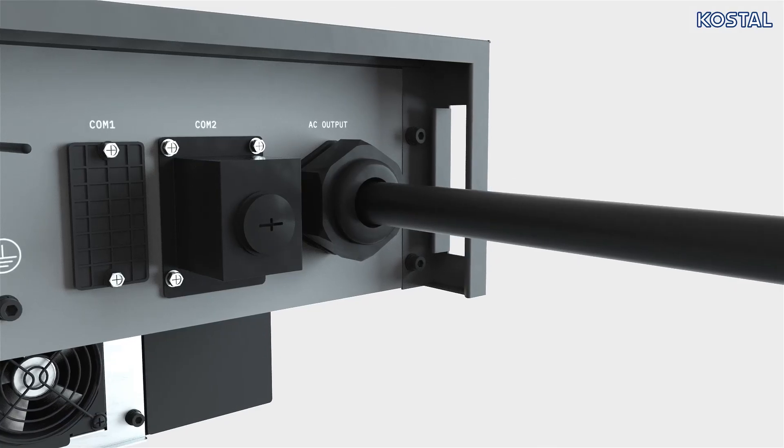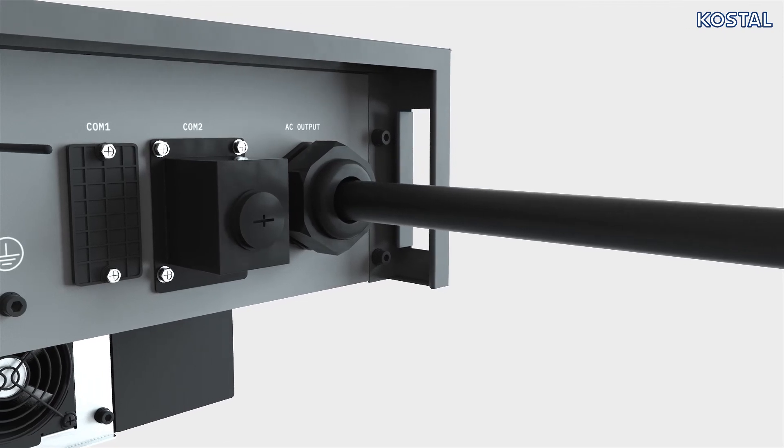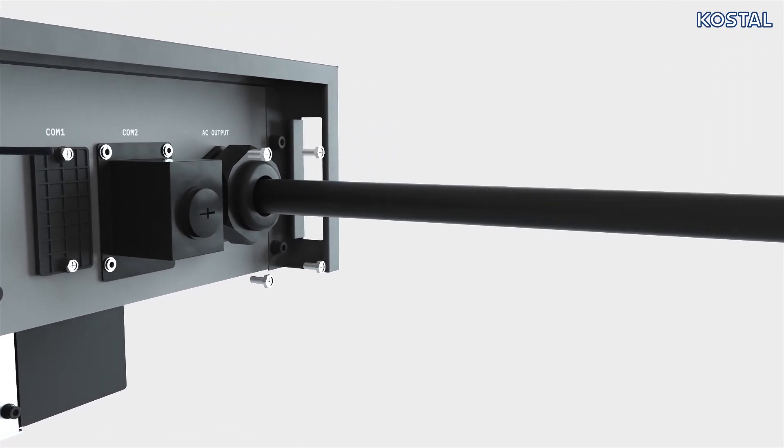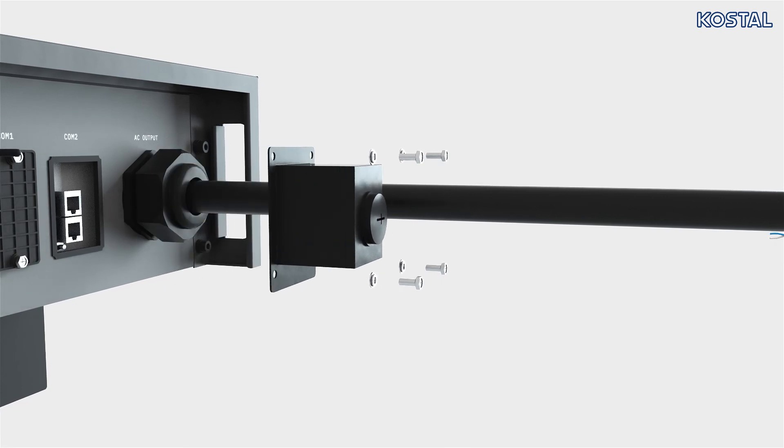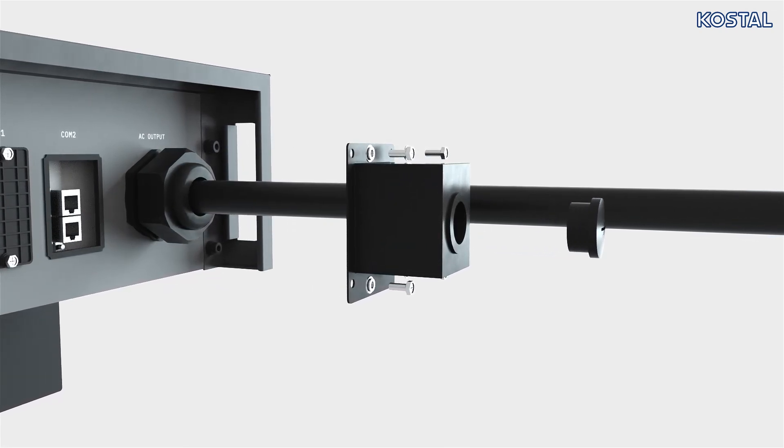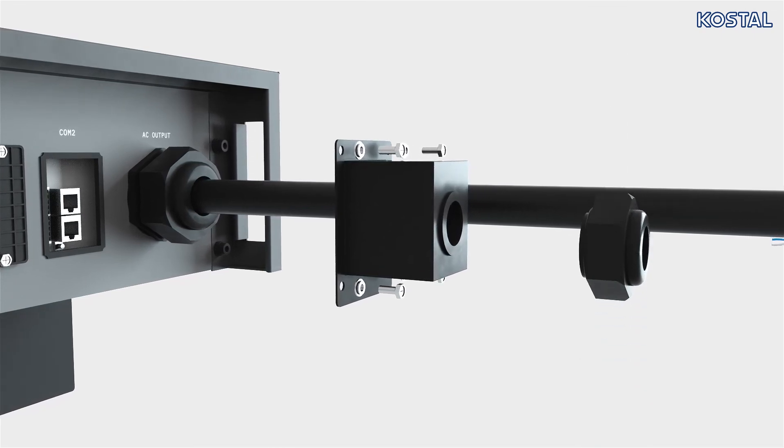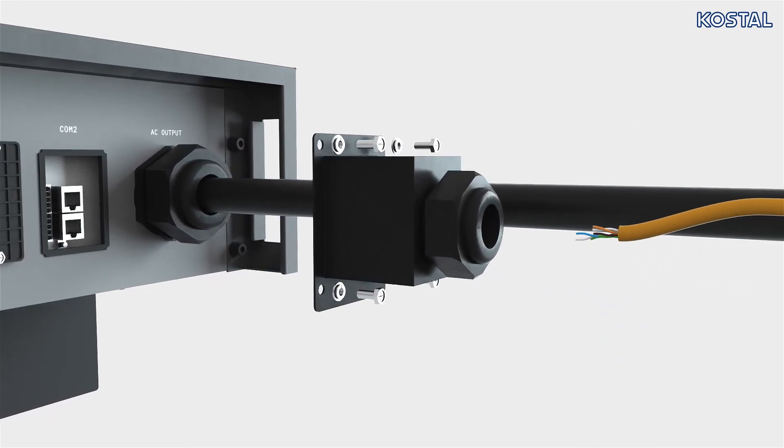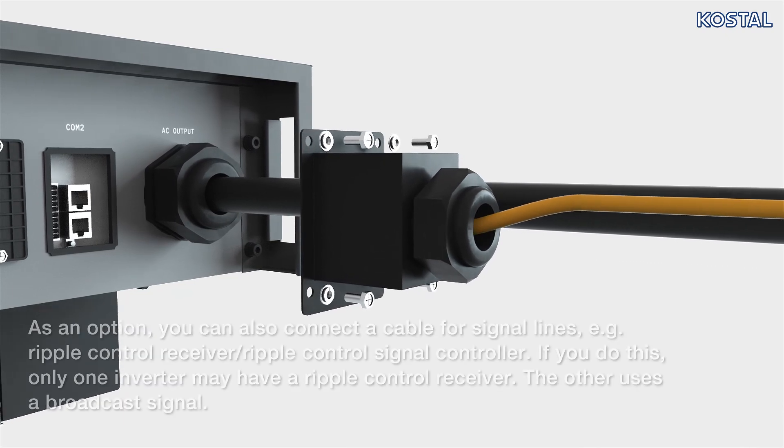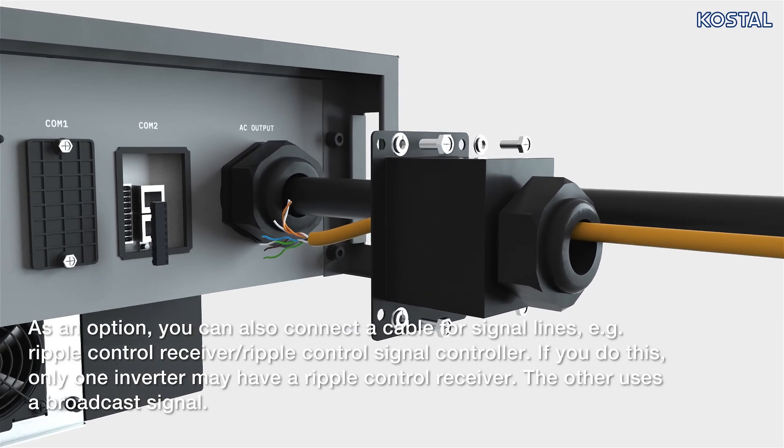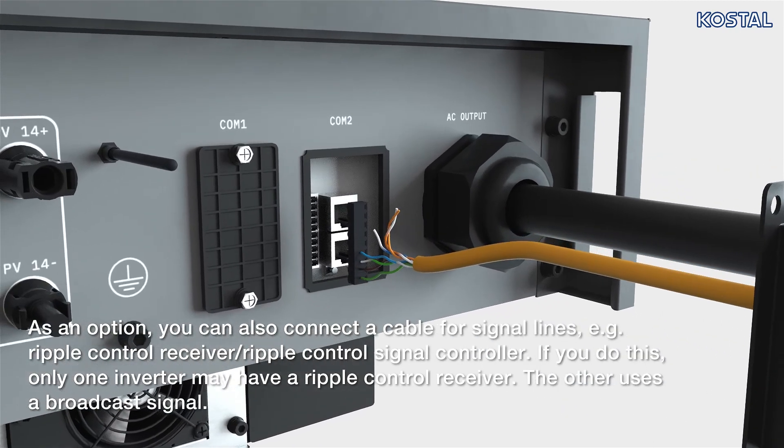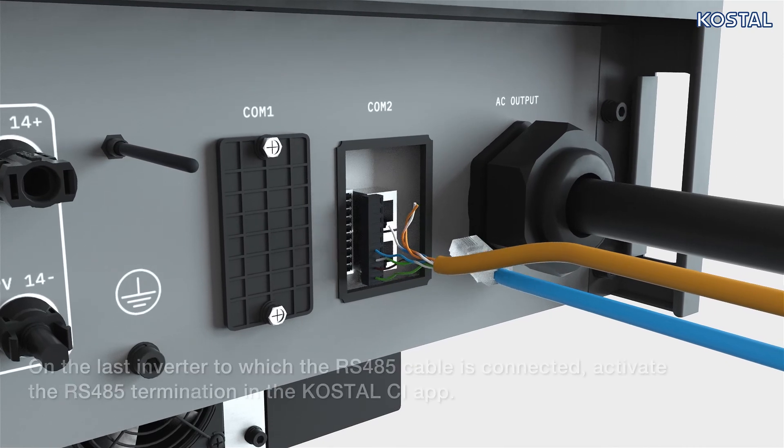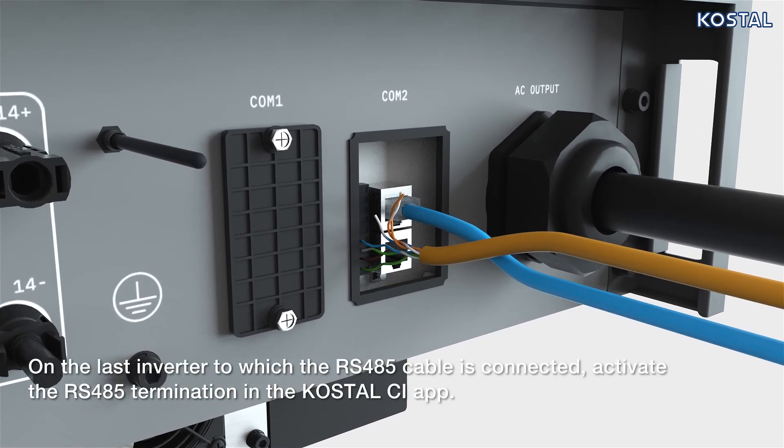Establish the internet connection with your inverter at the COM2 connector panel. Start by releasing the screws from the cover and removing the cover. Remove the plug seal and replace it with the appropriate plug with multiple ducts, which is supplied. Guide the Ethernet cable through the COM2 cover and connect it to one of the two LAN RJ45 sockets. Seal the LAN cable with a sealing ring and union nut.